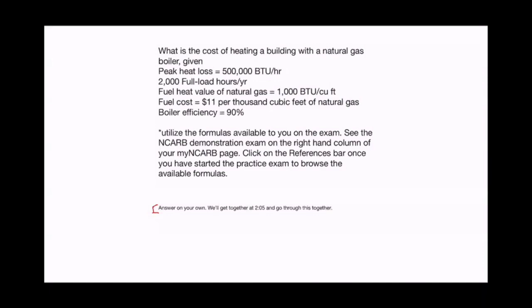And our question today is, what is the cost of heating a building with a natural gas boiler, given that peak heat loss is 500,000 BTUs per hour, that there are 2,000 full load hours in a year, that the fuel heat value of natural gas is 1,000 BTUs per cubic feet, that the fuel cost is $11 per 1,000 cubic feet of natural gas, that the boiler efficiency is 90%. And I encourage you to utilize the formulas available to you on the exam.